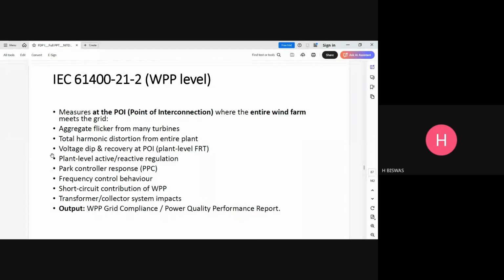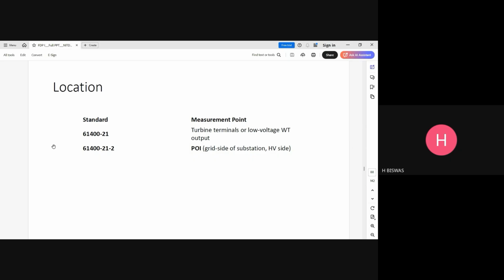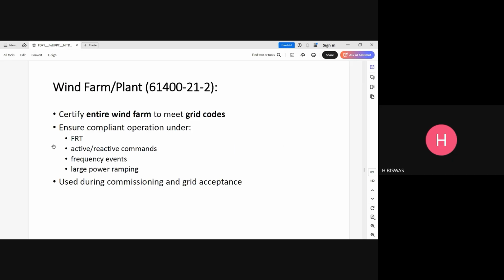So, aggregate flicker from many turbines, total THD, we call it total harmonic distortion from the entire plant, then voltage dip and recovery at POI, plant level active and reactive regulation, PPC, park controller response, frequency control behavior, short circuit, WPP transformer and collection system impact. The output is the WPP grid compliance and power quality performance report. So 21, part 1 and 2. The difference is POI. That's where the plant level we need to look forward.